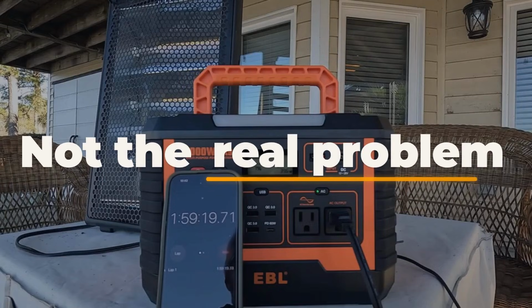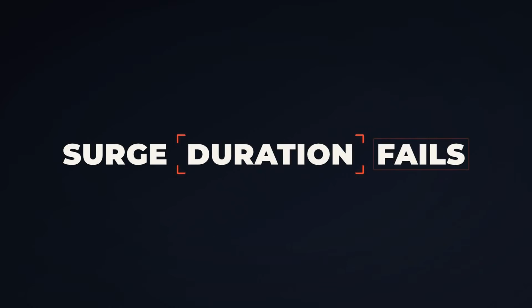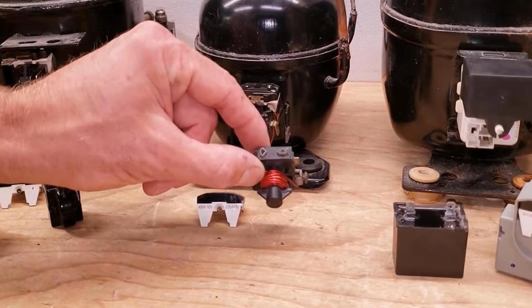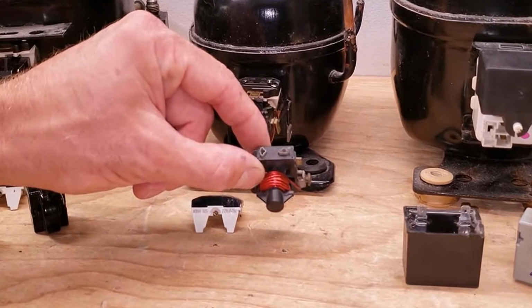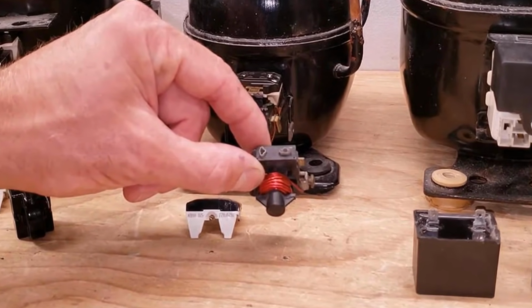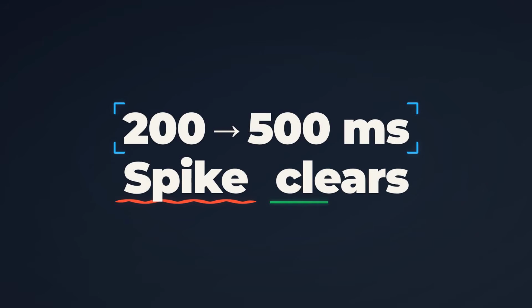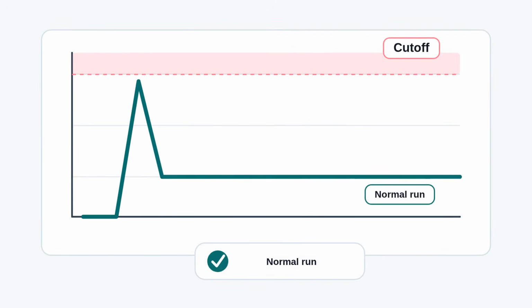That distinction matters, but it is not even the real problem. The real problem is surge duration. When a refrigerator compressor starts, it pulls 2 to 3 times its running current for a brief window, typically 200 to 500 milliseconds. That spike has to clear before the compressor can settle into normal operation.